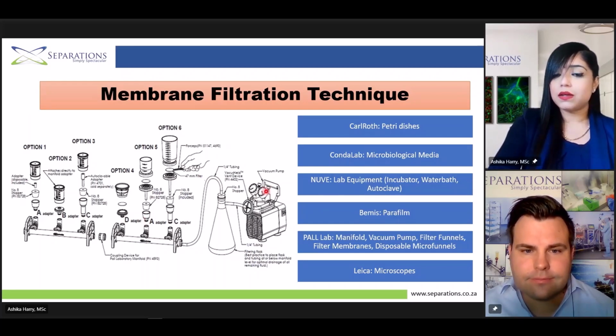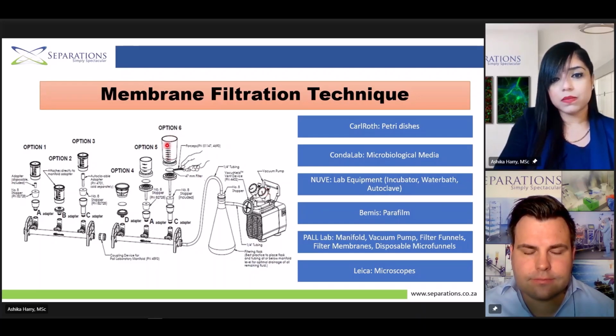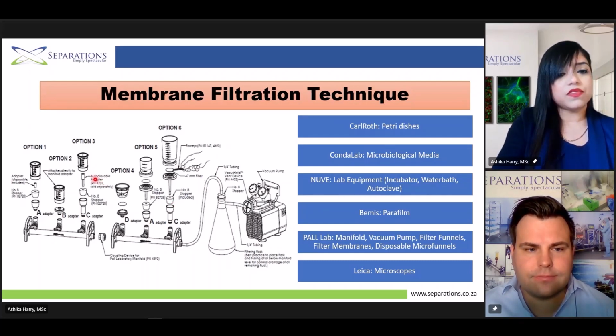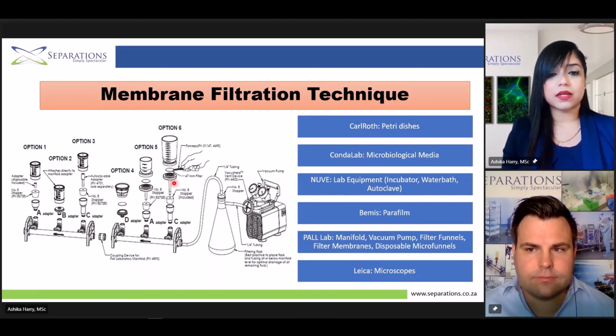Awesome. So basically how this works is you put your sample into your microfunnel, and then you switch on your pump. Your sample flows through your manifold and then collects into your collection flask. Once the sample has filtered through, you switch off the pump. The other feature of the microfunnels is that they are made of plastic, so they're easily squeezable, and this can also be done with one-handed operation. Then after your sample has filtered through, you take your membrane out and put it on a petri dish which also has culture medium, and similar to the other techniques, you seal this nicely and then incubate it for the required amount of time.